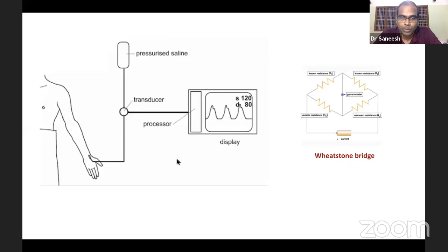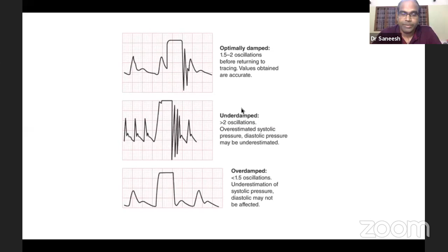Here you can see the optimally damped tracing, which settles after 1.5 to 2 oscillations after the pigtail is pulled. So the values are concordant. So this is optimally damped. Underdamped takes more than 2 oscillations. So this overestimates the systolic pressure, while the diastolic pressure may be underestimated. If it is overdamped, the tracing settles after less than 1.5 oscillations. There will be underestimation of systolic pressure, while diastolic pressure is not much affected. So maybe it can appear in your OSCE questions or in the skill stations.